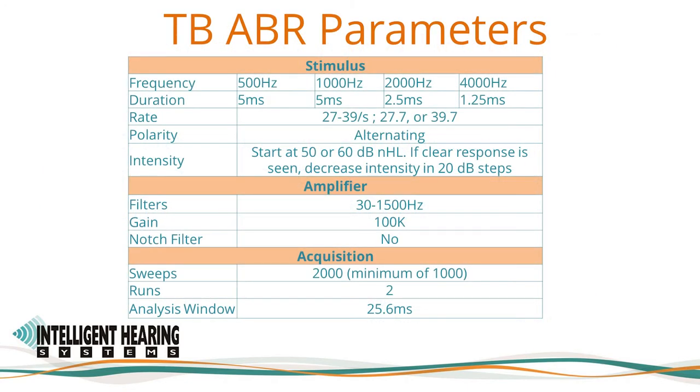The parameters are stored in the SmartEP software as settings files. Sample settings files are provided with the machine and can be loaded via the Load Settings option. We will use a 5 millisecond duration for the 500 and 1000 Hz tones, a 2.5 millisecond duration for the 2000 Hz tone, and a 1.25 millisecond duration for the 4000 Hz tone. The Academy Practice Guidelines recommended stimulus rate is between 27 to 39 per second, for example 27.7 or 39.7 per second. We use alternating polarity for the tonebursts. For clicks, alternating polarity helps distinguish neural portions of the response from cochlear portions such as the cochlear microphonic.